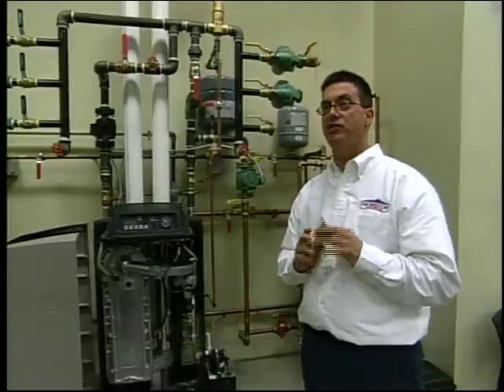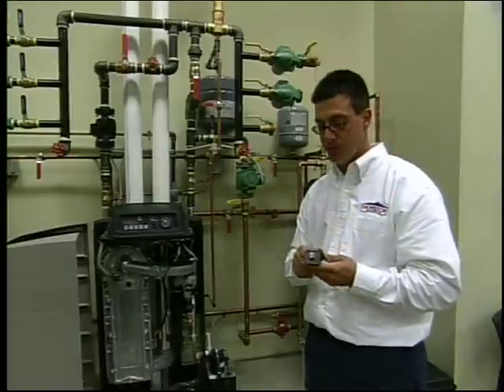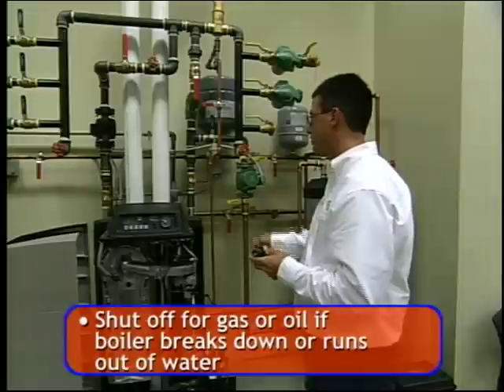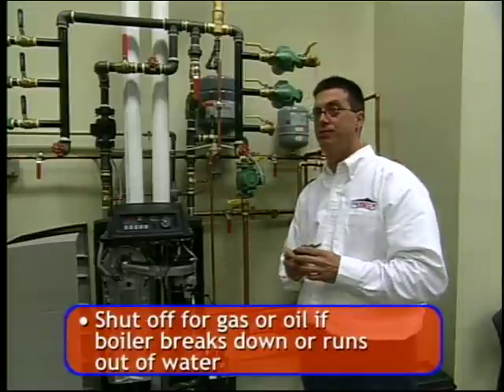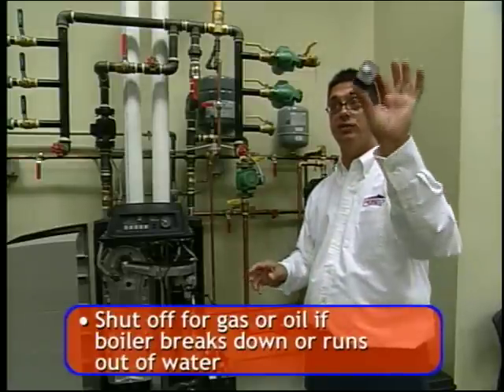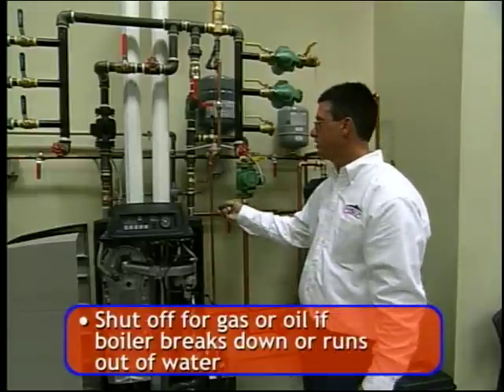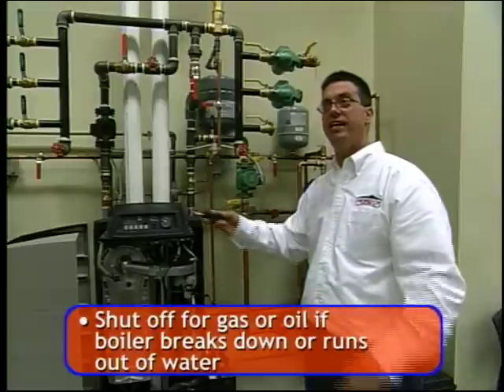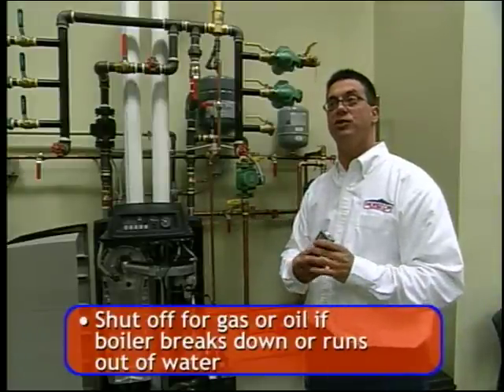Let me tell you about another safety device that we use on every one of our installations as a non-negotiable installation standard. A simple device that'll keep your boiler from firing in the unlikely event that the water escapes your system. Matter of fact, most boilers out there in America don't have these devices installed on them. In the unlikely event that your boiler should run out of water, it shuts down the gas or the oil instantly. What that means to you is that you don't have an uncontrollable fire in your basement at any given time.